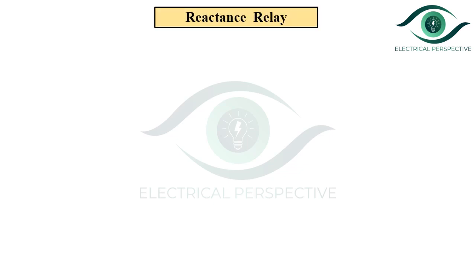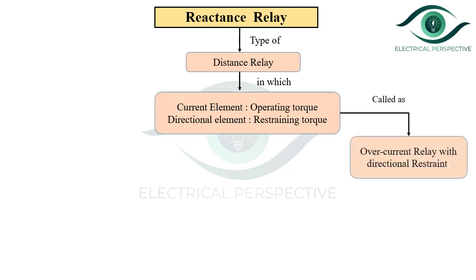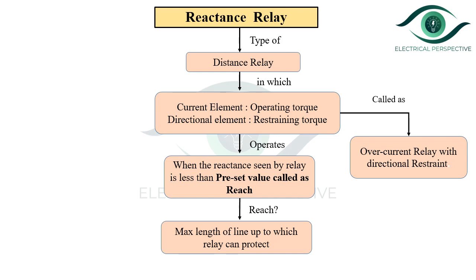Let us start with the introduction. The reactance relay is a type of distance relay in which the current element provides the operating torque and the directional element provides the restraining torque. It is also called an overcurrent relay with directional restraint. It operates when the reactance seen by the relay is less than the preset value called the reach, which is the maximum length of the line up to which the relay can protect.